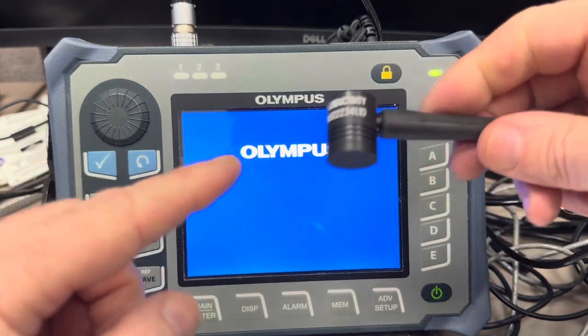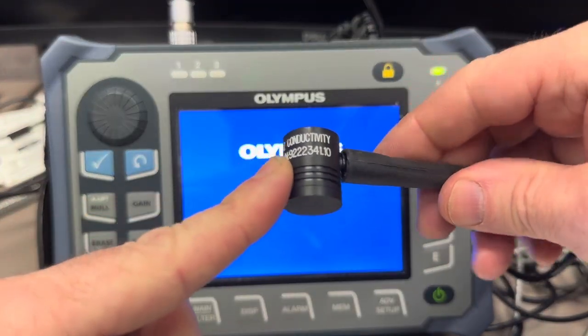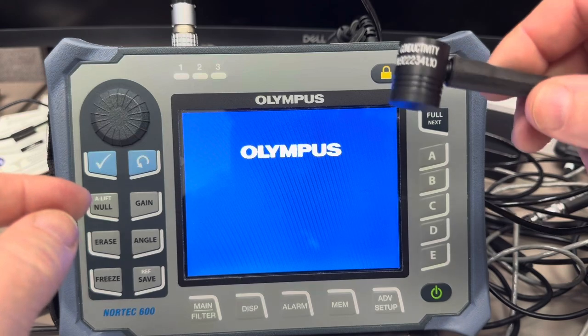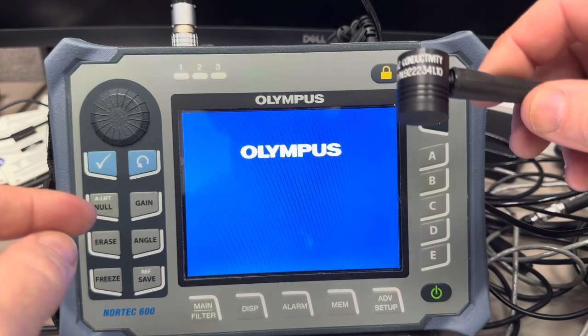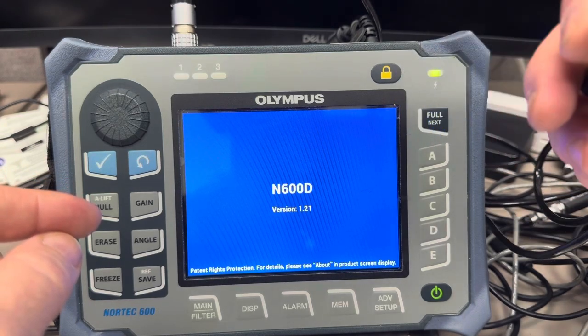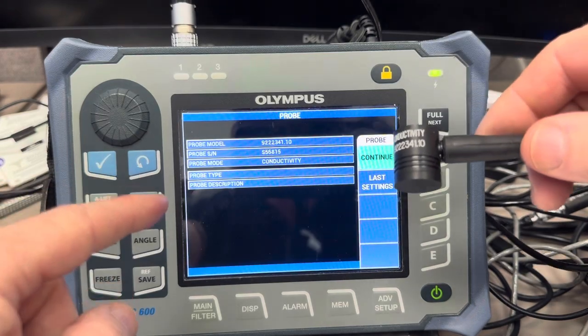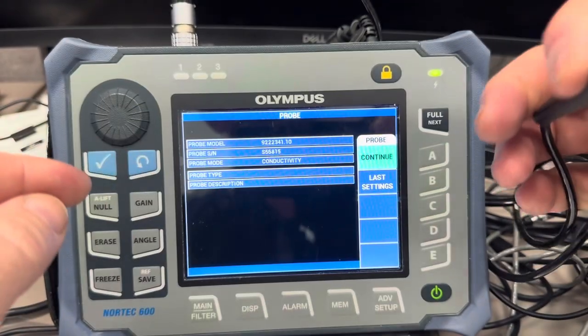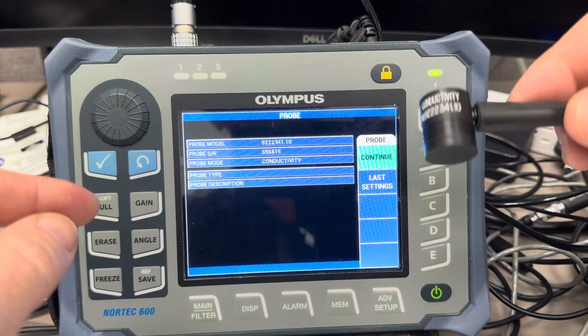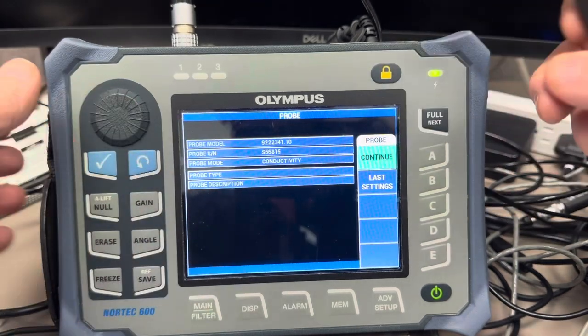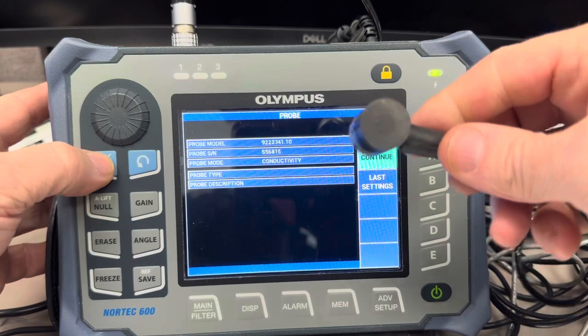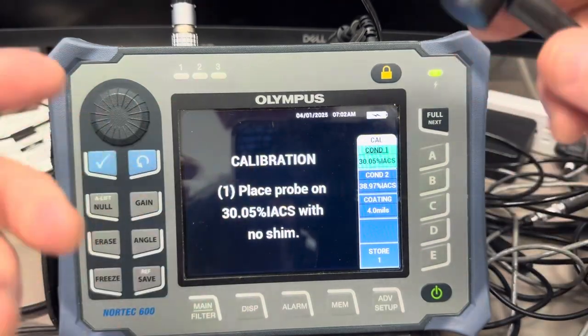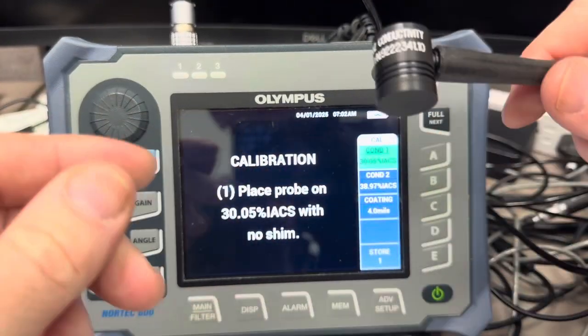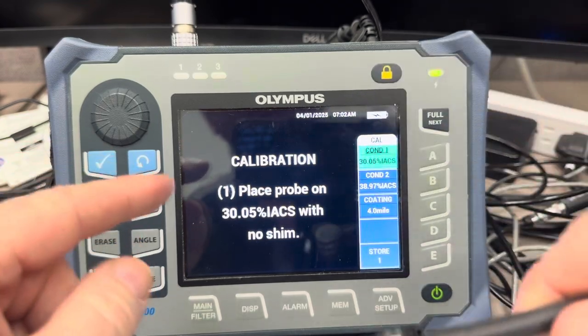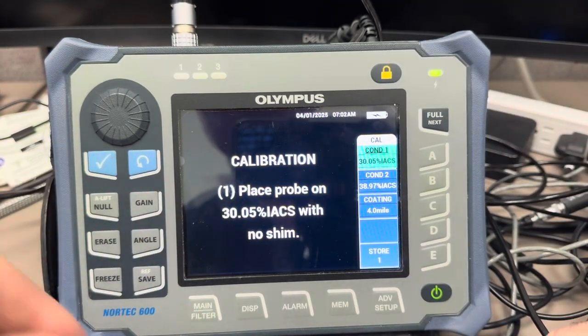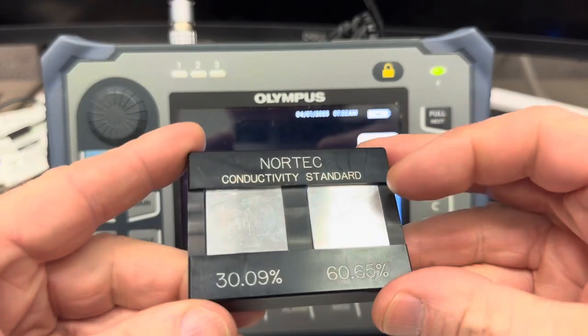So I'm going to turn on the tester, and this probe has a smart chip in it, so it works with the PowerLink feature of the Nortec instruments, and it's going to recognize the probe, serial number, model number. It lists it all right here, so you can confirm that the PowerLink and the chip is working correctly, and it is. So I'm going to hit continue, and I'll hit the check mark. So the system knows that we're going to be setting up for calibration based on the type of probe that I have hooked up. So it says place the probe on 30.05% IACS with no shim.